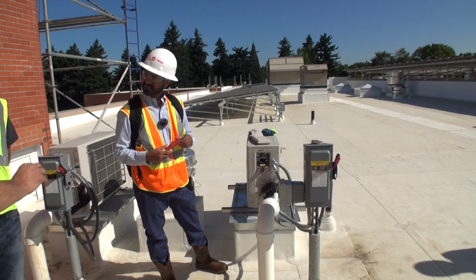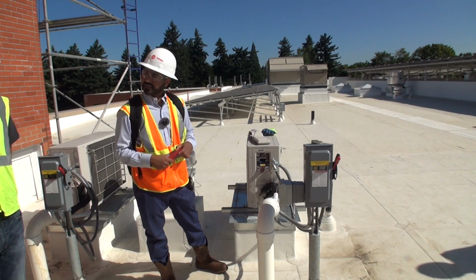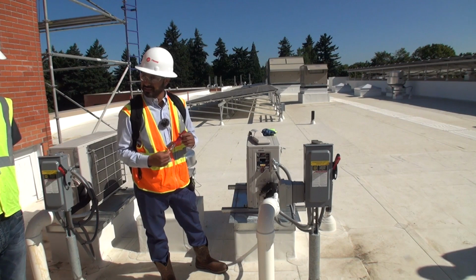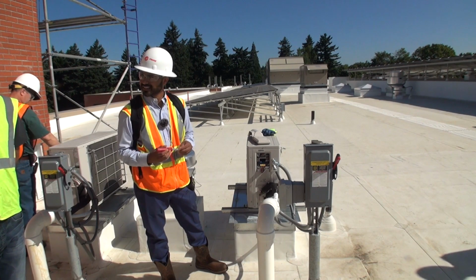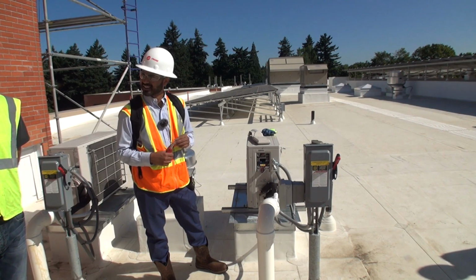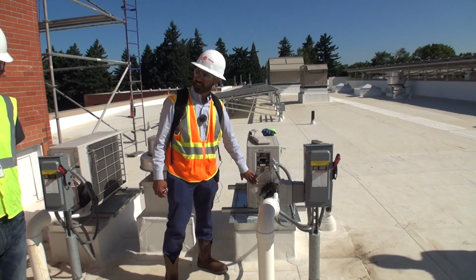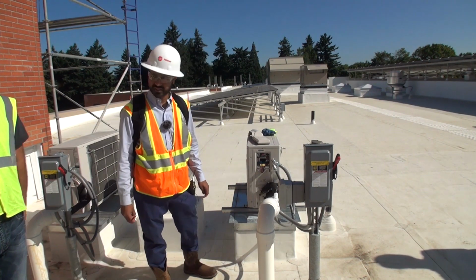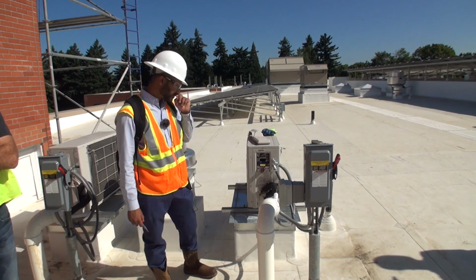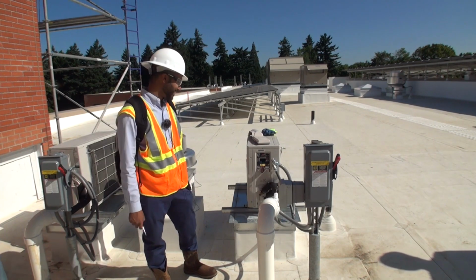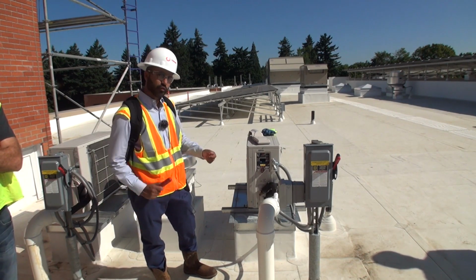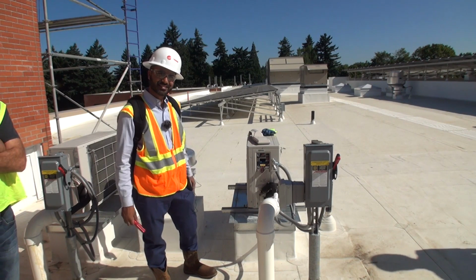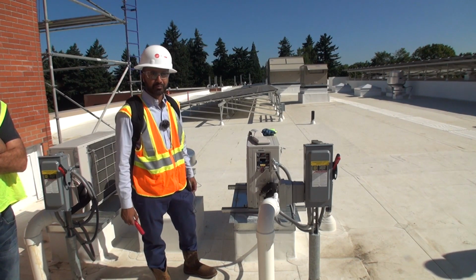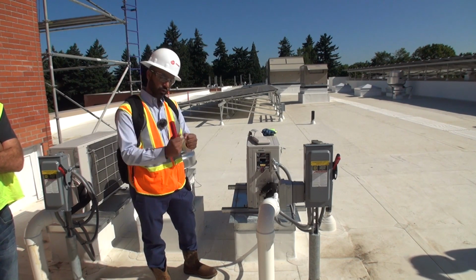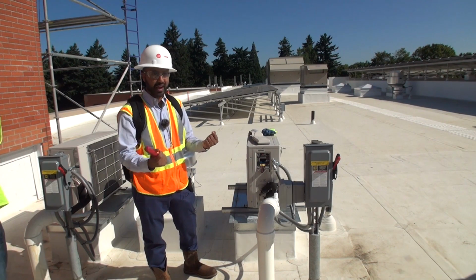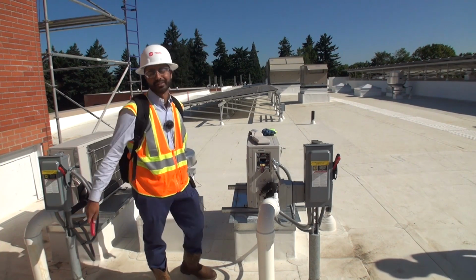Those flares are kind of known for leaks, aren't they? Flares, yeah, depending on how well they're done, they can leak. I just need to know refrigerant levels and stuff like that. Sure, and they should be listed on the unit. I've seen that in multiple places. I've seen guys torque them. Over torque them? No, like they have a torque wrench. Yeah, you do have to torque them. There's a lot of people who will just over torque them, and it doesn't feel right, even with the factory settings. So it is what it is.